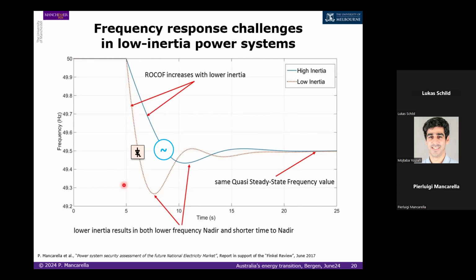The frequency, normally 50 hertz, can go down very, very fast. And the more power electronics interfaces you have, the faster it goes down, because it effectively displaces the synchronous machines that provide physical stability through the so-called inertia present in the spinning masses of the power system.